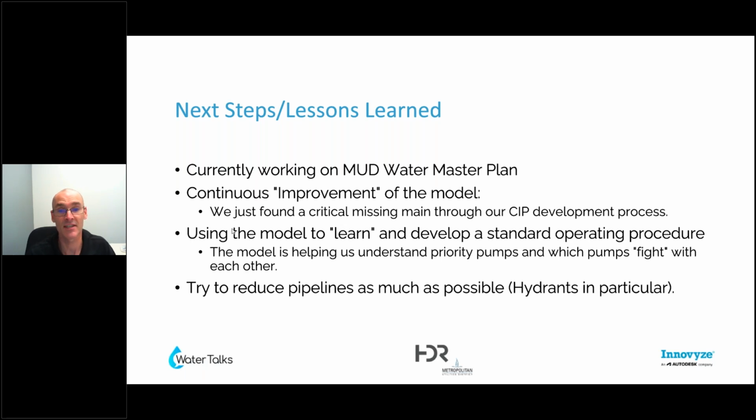You can go in and see, through the simulation output results, which facilities are fighting with each other. So it's really helping us in the master plan point them in the right direction: you should really be operating these pumps as a priority, and we should really think about VFDs in these areas, and it'll help you in the long run.